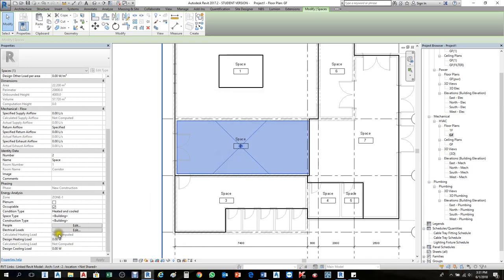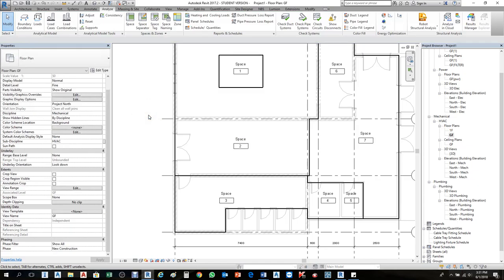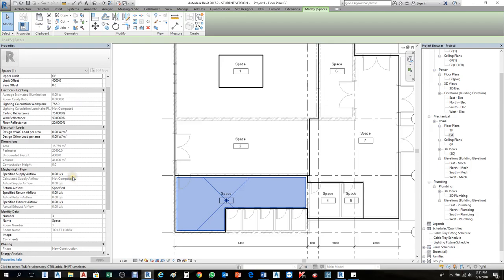Press OK. Going down, design cooling is 0 watts. Any mechanical information you have you can fill in here so it will give you the calculated air flow. For instance, if this room gives you a calculated air flow of 1000 ls (liters per second), when you place air terminals you follow that target of 1000. If one air terminal handles 250 ls, you'd need four terminals. You place them one by one until you reach the limit, then stop adding air terminals to the room.